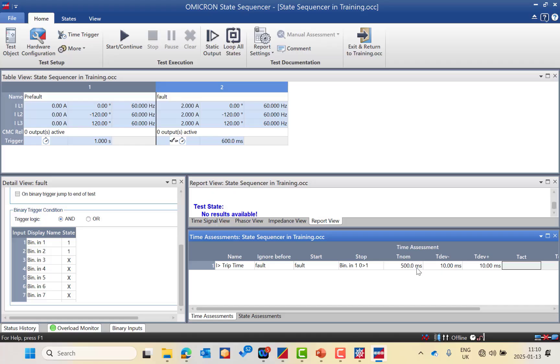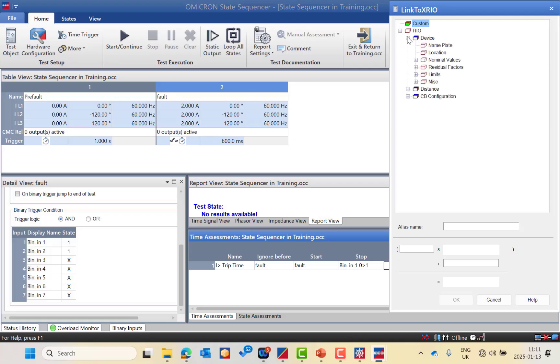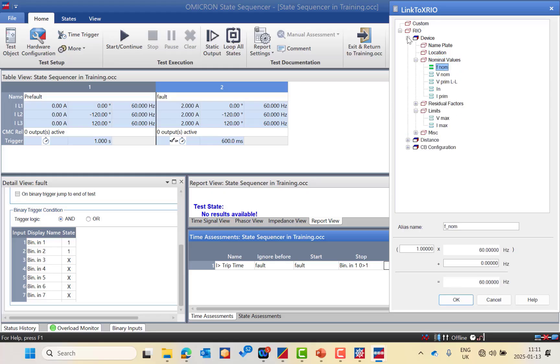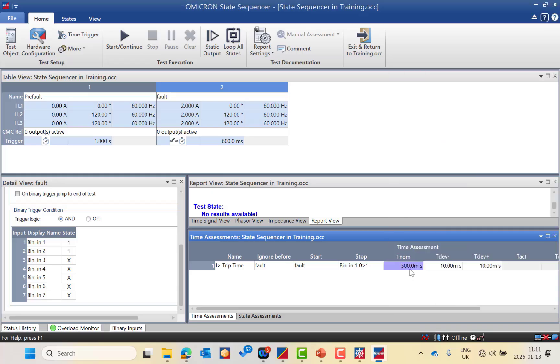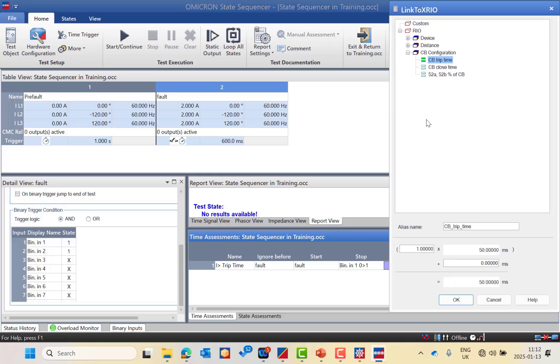The manual assessment is created and automatically linked. If I need to link the 500 ms value to a parameter setting, I can link to XRIO and choose the time — for example, the CB trip time of 50 milliseconds. I can use a multiplier (1, 1.1, 1.2) and add a minimum operating time offset, and it will be automatically linked. The value color switches to purple, indicating it is linked. Hovering with the cursor and selecting 'go to linked value' or 'place linked to XRIO' will show which value it is linked to.